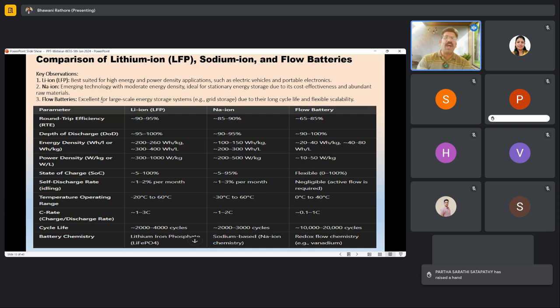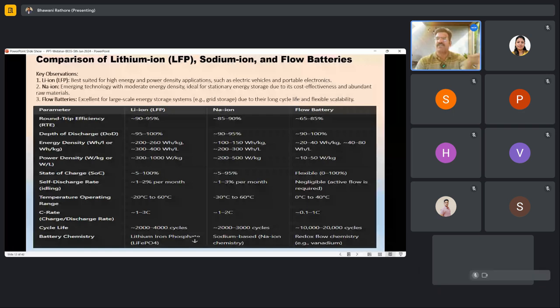Flow battery is excellent for large scale energy storage and grid storage due to its long life, with 6 to 7 hours of backup storage. With lithium ion, we go with either 2 hours or 4 hours. In the last webinar I showed 1000 MW / 4000 MWh, which is 4 hours of energy storage, or 50 MW / 100 MWh, which means 2 hours of energy storage. But with flow batteries, we can go up to 6, 7, or 8 hours of storage. The electrolyte remains in liquid form and is stored in a tank.